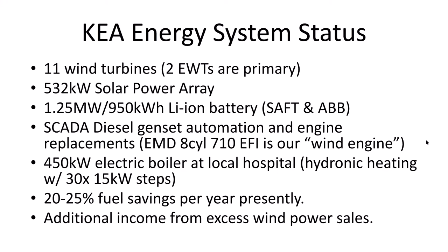We also have an electric boiler at the local hospital, so we're doing something called beneficial electrification. Whenever we have too much wind power, instead of not capturing it—which we could do by pitching the wind turbine blades to reduce power output—we instead capture as much wind as possible and sell electric heat to the local hospital. That's been in place for about 3 or 4 years now, reducing their diesel fuel consumption annually by about 25 to 30,000 gallons a year.